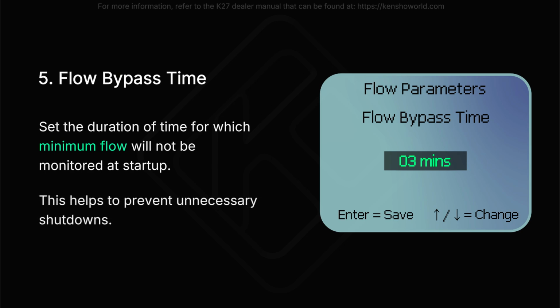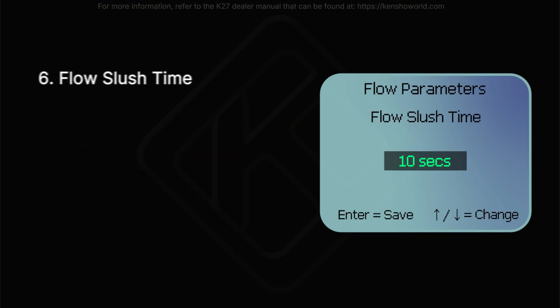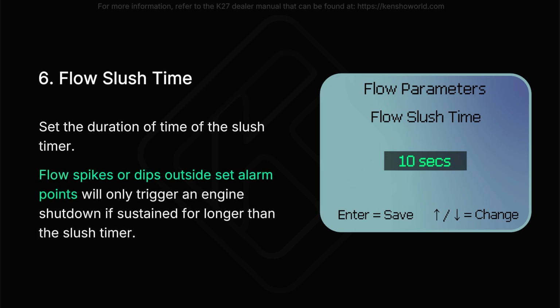Use the flow bypass function to set the duration of time for which low flow will not be monitored at startup. This helps to prevent unnecessary shutdowns. Set the duration of the slush timer here. Flow spikes or dips that fall outside the set alarm points will only trigger an engine shutdown if sustained for longer than this timer. Here you can calibrate your sensor to correct offsets, so that 4 mA corresponds to 0 flow.